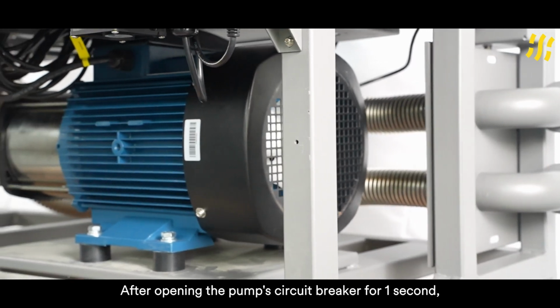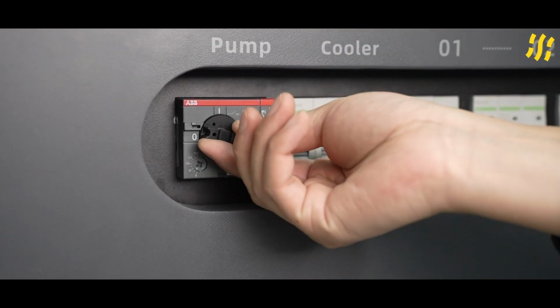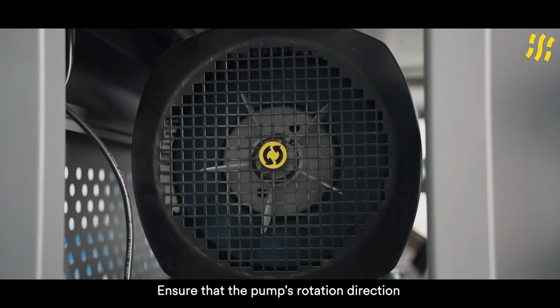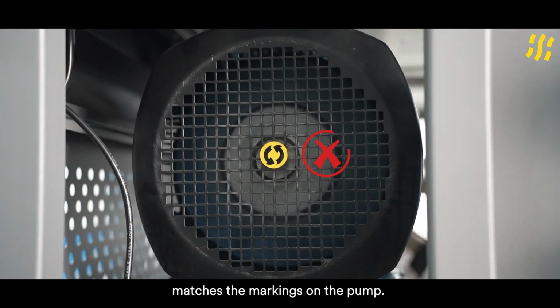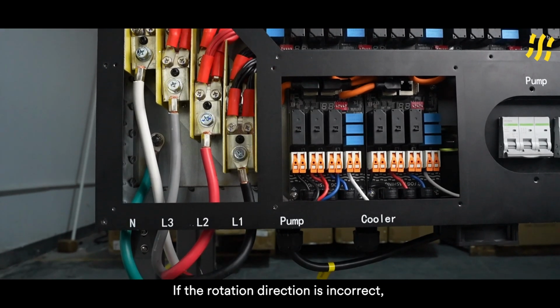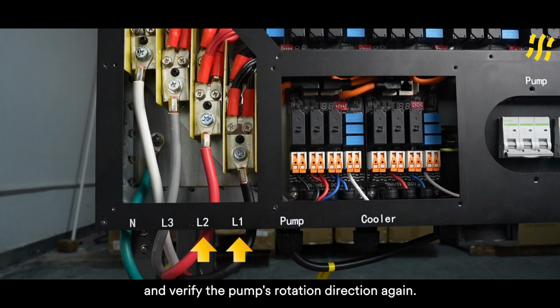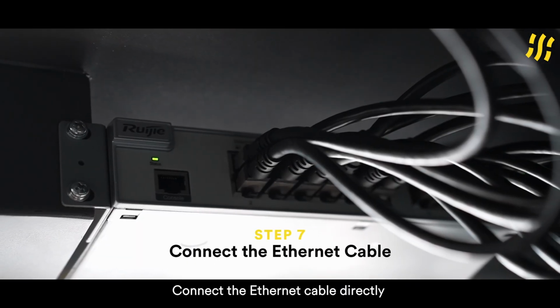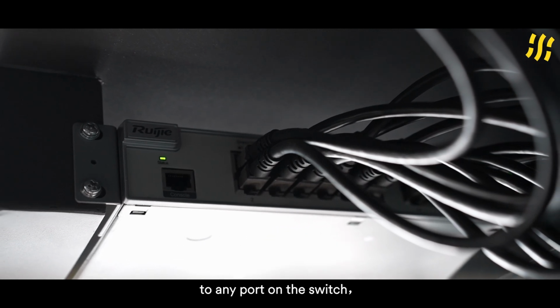After opening the pump circuit breaker for 1 second, please close it again. Ensure that the pump's rotation direction matches the markings on the pump. If the rotation direction is incorrect, swap the L1 and L2 connections and verify the pump's rotation direction again. Connect the Ethernet cable directly to any port on the switch.